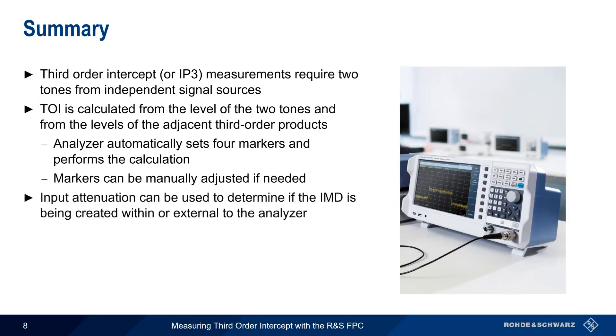In some cases, we may need to manually adjust the markers. Finally, we can change the level of input attenuation to determine if the measured intermodulation distortion is coming from the device under test, or from the analyzer itself.